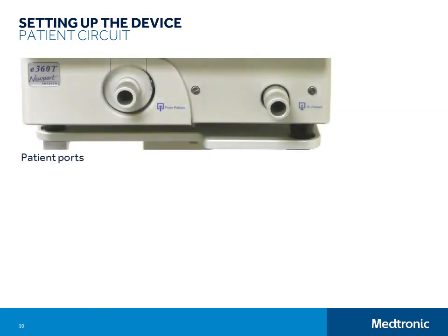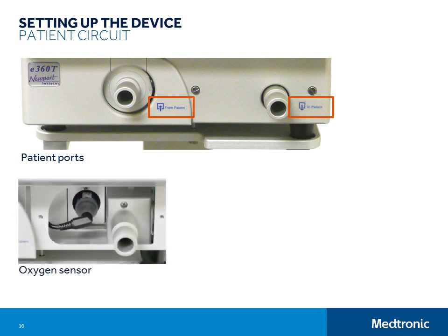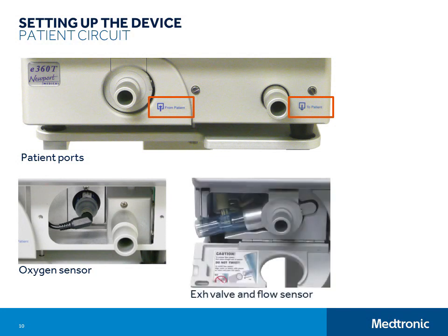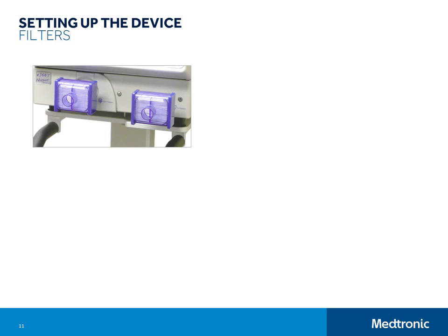Let me take a minute to orient you to the layout of the tubing ports before we go over attaching the breathing circuit system. You will notice that there are labels on the tubing ports that say to patient and from patient. These labels indicate the direction of flow. So tubing going to the patient will connect to the port on the right, and tubing coming from the patient will connect to the port on the left. The oxygen sensor is located just behind the to-patient port, and the exhalation valve and flow sensor are located just behind the from-patient port. Start your breathing circuit setup by attaching filters onto the to-patient and from-patient ports.